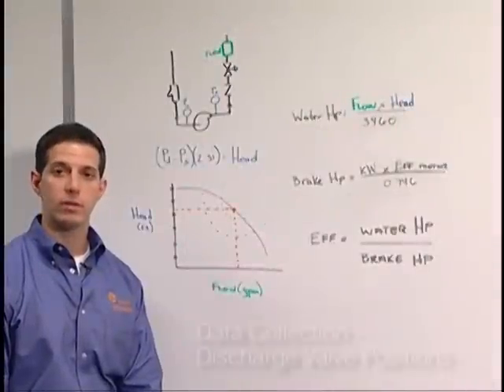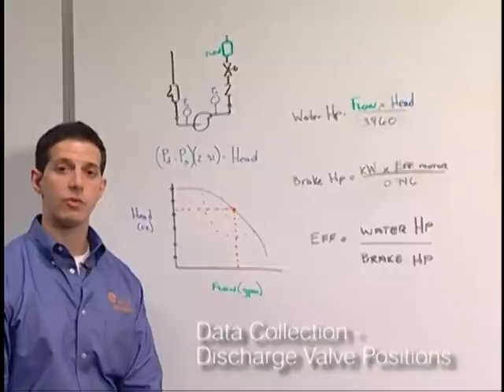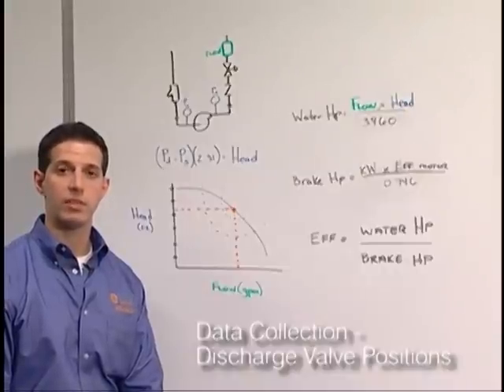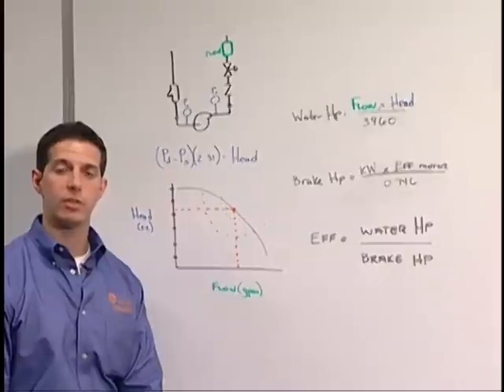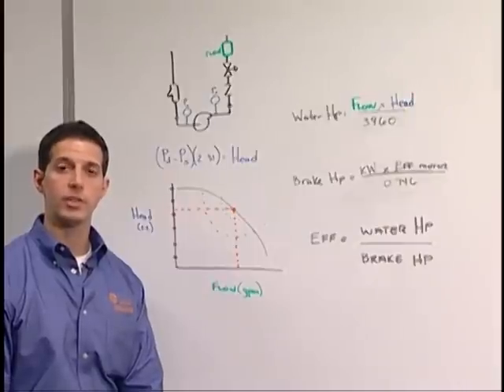When recording pump data, it's important to collect three different readings. The first is the as-is condition. Then, slowly close the discharge valve until it's completely shut. We call this the dead head position.